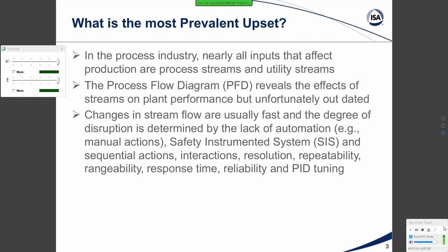Of course, you would prefer that the flow measurement have the best rangeability, and that generally is associated with magnetic flow meters and especially with Coriolis meters being the exceptional example of how great the rangeability and repeatability and maintainability is. Often, if you get the right Coriolis meter, you don't need to do much after getting it initially calibrated, and even the installation requirements are rather minimal.